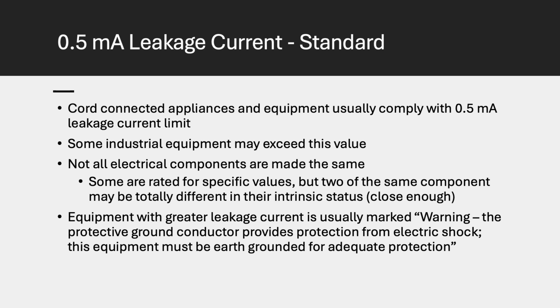Just like water hoses, electrical components like wires can leak electricity as well. It's how much current flows out that is the issue. The industry standard for electric devices is half a milliamp of leakage current. However, when it comes to heavy-duty industrial equipment, some may exceed that value.